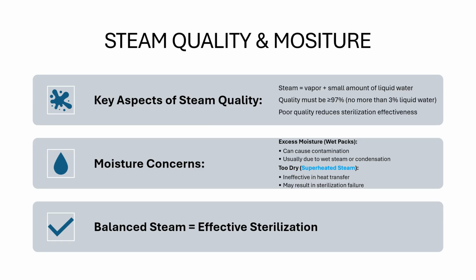The quality and the moisture. Steam quality is crucial in high temperature sterilization. It's defined by the proportion of vapor to water. Optimal steam should be at least 97% vapor. Excessive water, which is over 3%, reduces the ability of steam to transfer heat effectively. That can also compromise the sterilization. Wet packs are a sign of poor steam quality or post-cycle condensation. So these packs are at risk for contamination and must be reprocessed.